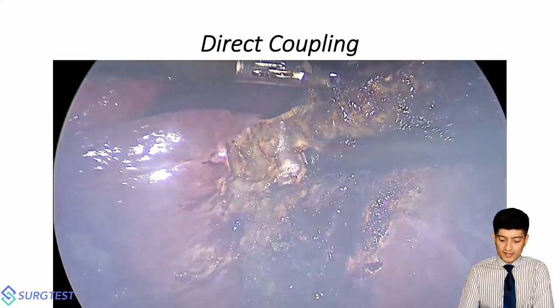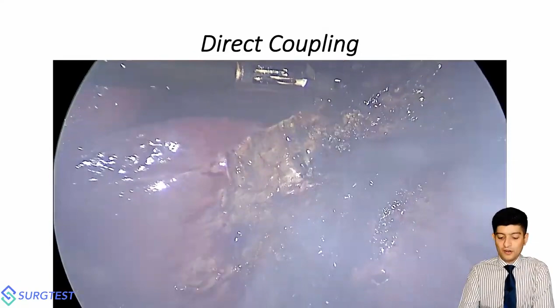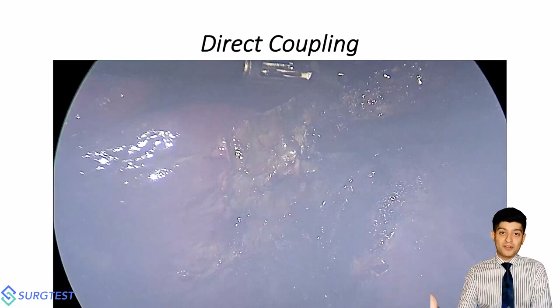So this is a patient where there is a problem with the insulation of the laparoscopic hook that is being utilized, and you can see the spark that got generated just by having another device close to it. Clearly, there is a coagulating current which is being used. I'm just going to show you that very quickly again. So they are trying to take the GB off the fossa. You can see there's already sparking happening, and there's a big spark when it comes in contact with the grasper. So this right now at least is happening within the field of view. When it happens beyond the field of view, you're risking all sorts of damage which is going to go unnoticed at the time of surgery.